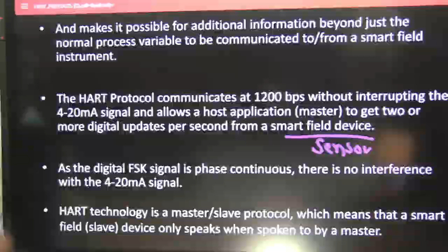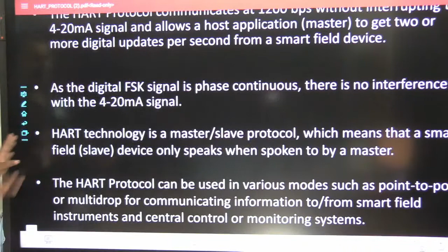And one more important point, the frequency shift signal is phase continuous, so there is no interference with the 4 to 20 milliampere signal. And most important, it uses the master slave protocol, the most successful one, which means that a smart field device only speaks when spoken to by a master. That means the master has control of the slaves. It can activate a particular slave at a particular time, and it can mask others. This masking concept is most important.